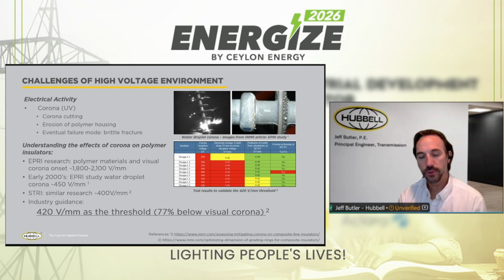So what I'm referring to here is that when a voltage level reaches a significant level on any object that's energized, it can reach a point where the air around the object begins to ionize, begins to break down. And that is understood through the manifestation of visual corona. And the picture in the top left, it is a black and white photo, so it's kind of hard to make out. But you're seeing those electrical discharges on the sheds of the insulator around the end fitting, and that is the manifestation of corona.